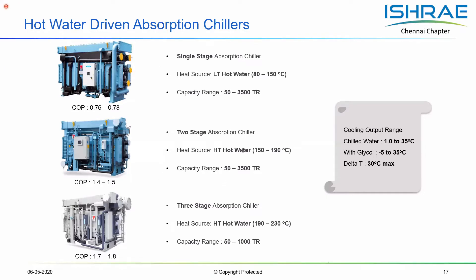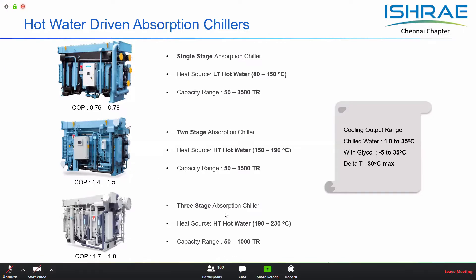Such technologies are gaining popularity as energy costs increase and there is continued focus on reducing carbon footprint and operational expenses. As a standard unit available in the market, a single-stage chiller is used for 80 degrees Celsius and above. For higher hot water temperatures of 150 degrees Celsius and above, you can go for either a two-stage or three-stage chiller. The chilled water generated is of the same order — down to 1 degree Celsius or minus 5 degree brine.